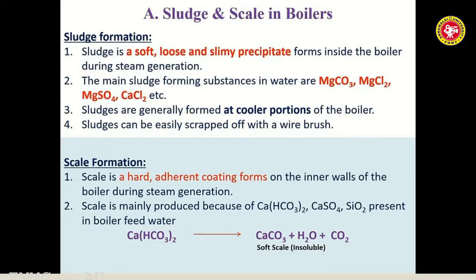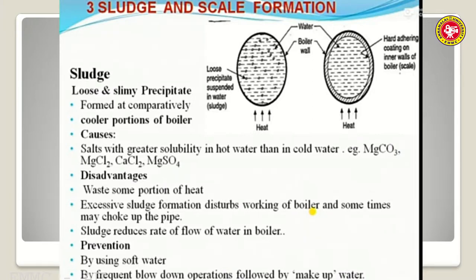What is scale? When you boil water in a beaker and forget to turn it off in time, the water dries up and the inner surface of the beaker is covered with a white, strongly adherent precipitate you cannot remove even by rubbing with a brush - that is called scale. Scale is a hard, adherent coating that forms on the inner walls of the boiler during steam generation. The reasons for scale formation are calcium bicarbonate, calcium sulphate, and silicon dioxide present in the boiler feed water.